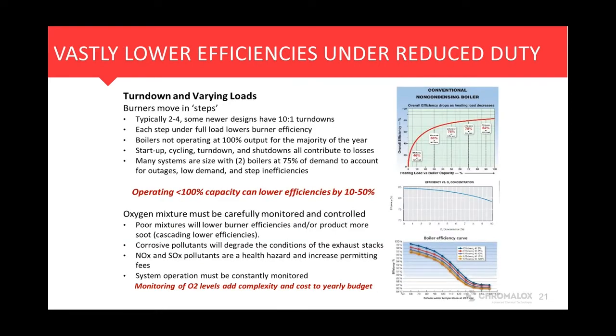Again, we look at the operational efficiency. I mentioned the study had looked at what it looks like at 100% load all year long, but we know that's not the case. We know loads change. So burner systems typically operate in steps, maybe 2 to 4 steps, and as they step down, their efficiencies decrease. Ideally you keep them at 100%, but if not, you'll see a decrease in the capabilities of the systems.